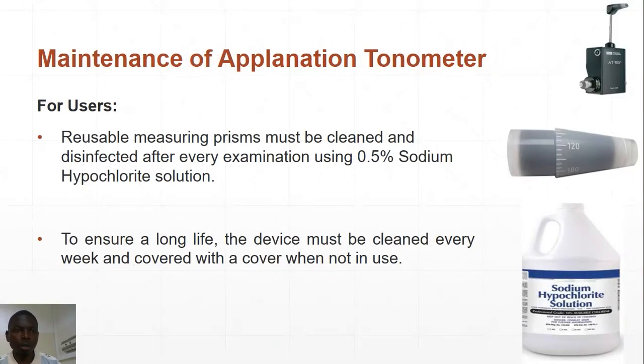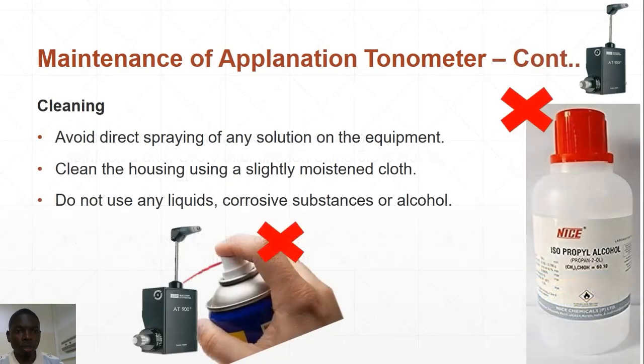Maintenance of Applanation Tonometer for users. These are things the user has to do from time to time. How to maintain the tonometer. The user must see that the reusable measuring prism is cleaned and disinfected after every examination using 0.5% sodium hypochlorite solution. To ensure a long life, the device must be cleaned every week and covered with a cover when not in use. The user must pay attention to all of this.